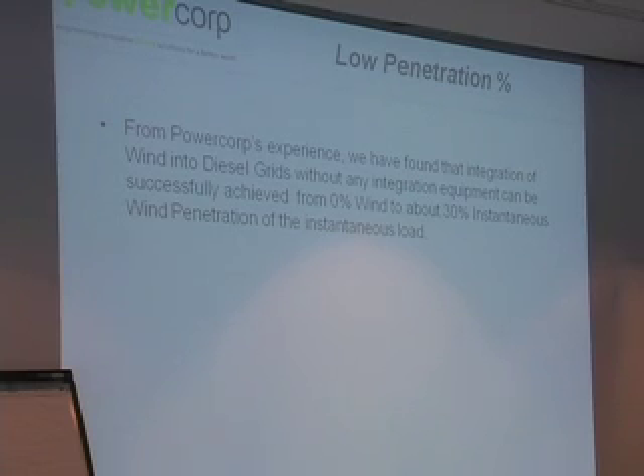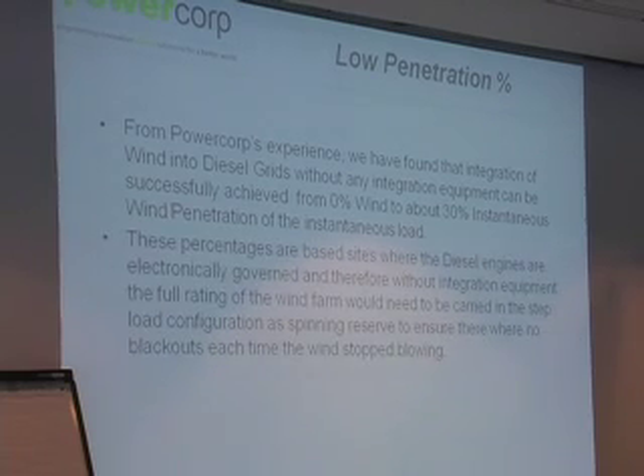It may or may not work in all cases. You might be able to put in a bit larger percentage. A low penetration from our point of view is in the order of up to 30% instantaneous wind penetration, meaning the governors can pick up the problems. We've based that on using electronic fuel injected engines these days, which are quite quick.